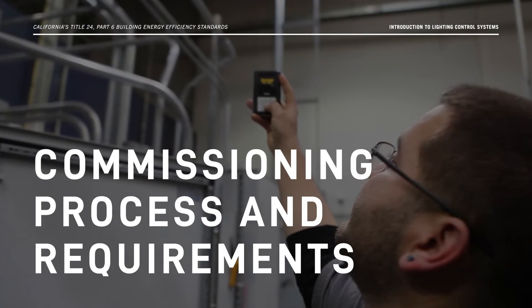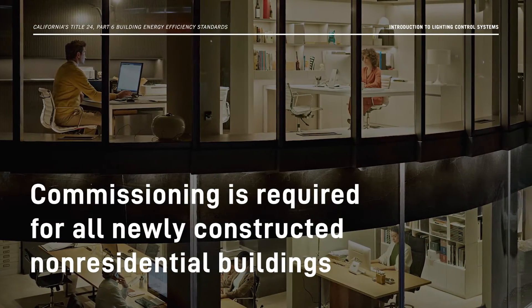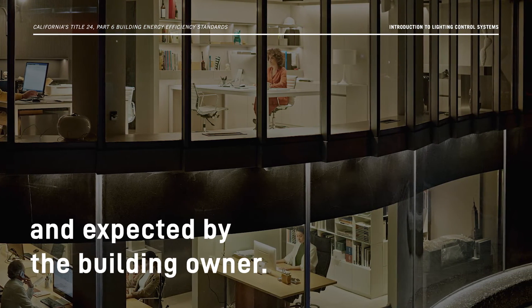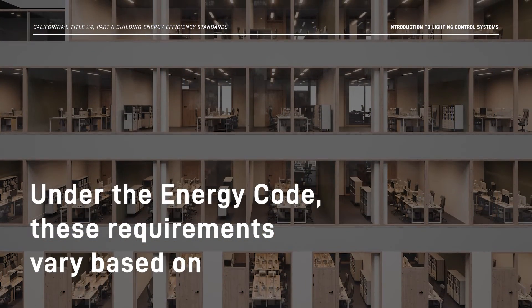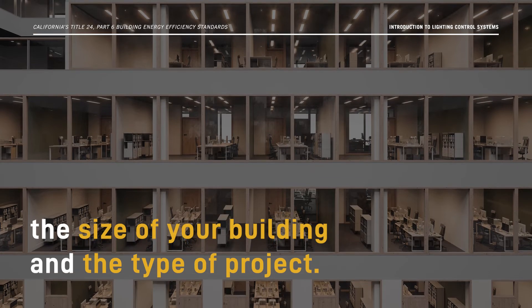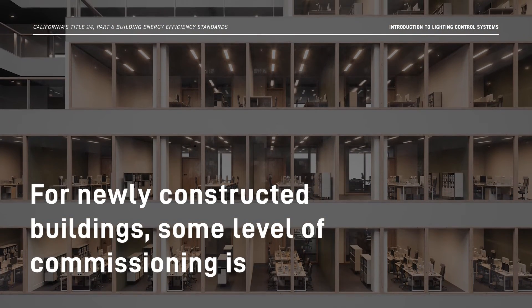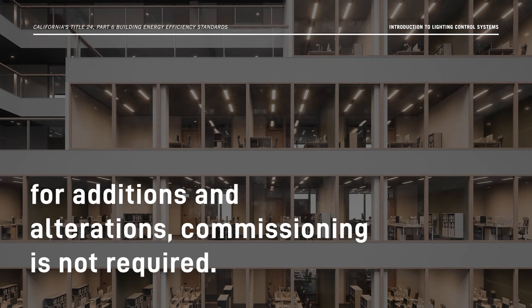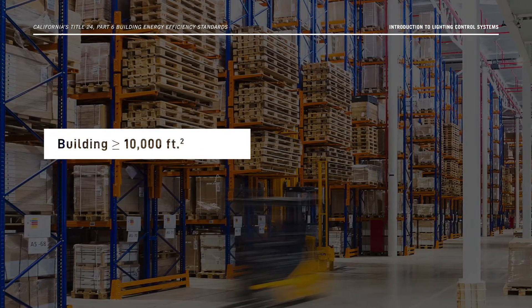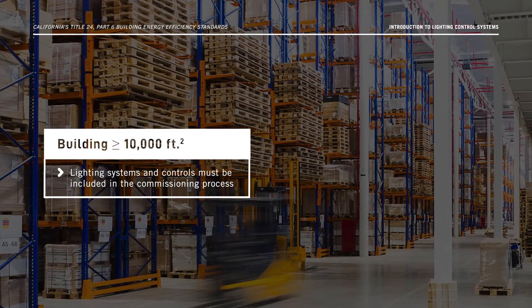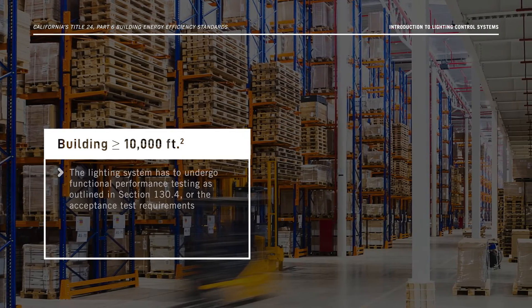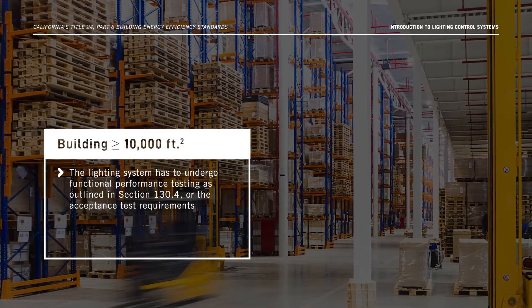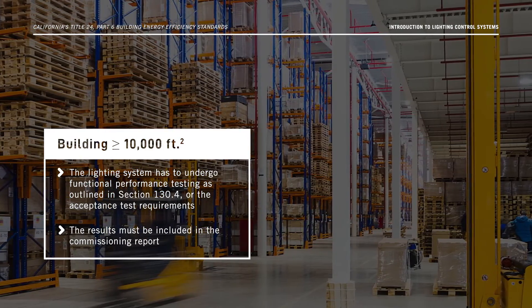Moving on to commissioning requirements. Commissioning is required for all newly constructed non-residential buildings to ensure that the controls operate as planned and expected by the building owner. Under the energy code, these requirements vary based on the size of your building and the type of project. For newly constructed buildings, some level of commissioning is always required for compliance, but for additions and alterations, commissioning is not required. If your newly constructed building is 10,000 square feet or larger, lighting systems and controls must be included in the commissioning process. The lighting system has to undergo functional performance testing as outlined in Section 130.4, and the results must be included in the commissioning report.